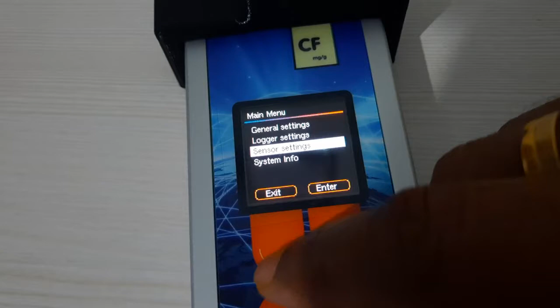So again we have to go to menu, sensor settings, enter calibration data, enter. 65, let us reduce it more. Let us do it at 61. Next, set, exit, measure. So it's again minus 0.03.